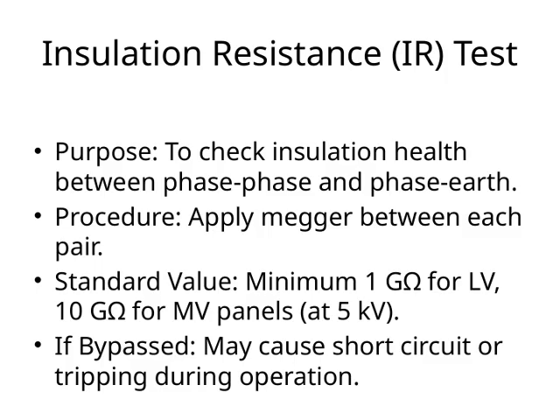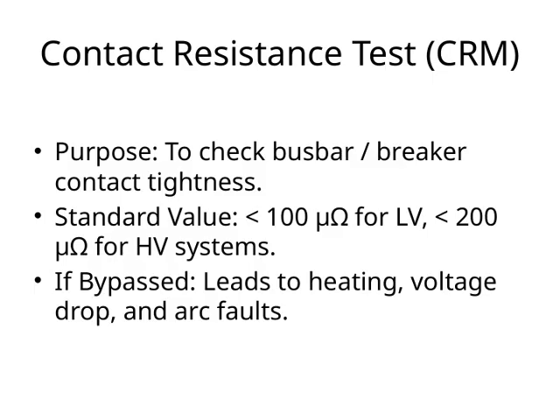electrical system running smoothly. Let's talk about the contact resistance test, or CRM. The main purpose of this test is to check the tightness of busbar and breaker contacts. Ensuring good contact is crucial because poor contact can lead to a number of issues. Now, in terms of standard values, for low voltage systems, the contact resistance should be less than 100 microohms, and for high voltage systems, it should be less than 200 microohms.